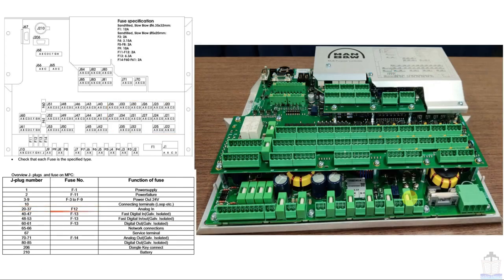Okay. Now moving to our next fuse, that is F13. F13 is located over here, and this F13 supplies the power from channel number 40 to 53. But here you can see that this is also supplying the channel number 60 and 61, but actually this is wrong. Channel number 60 is being supplied with the F60 and channel number 61 is supplied with the F61. So you can see here like this, channel number 60 supplying with the fuse number 60, channel number 61, fuse number 61. Okay, so please take care of this one.